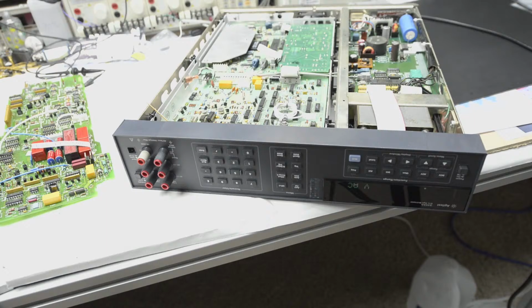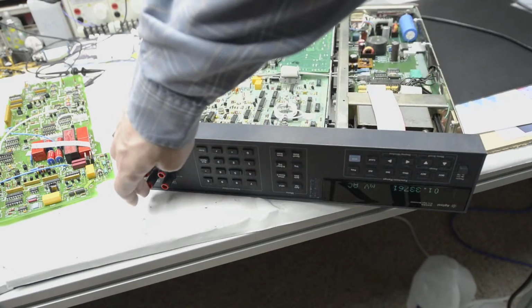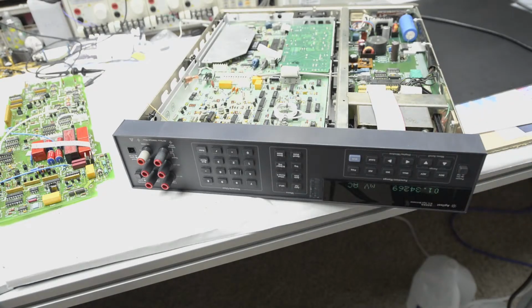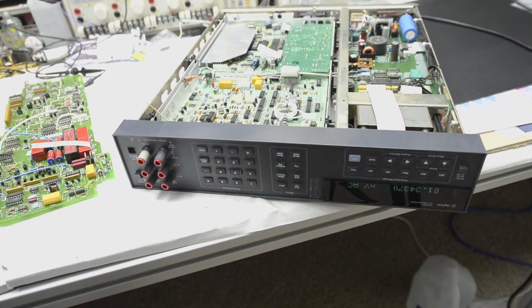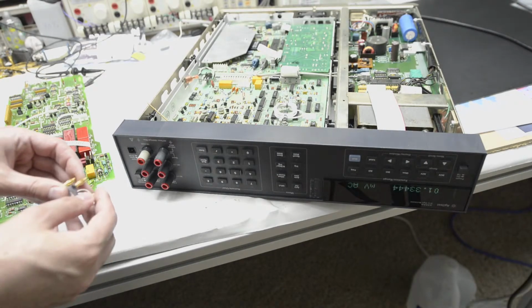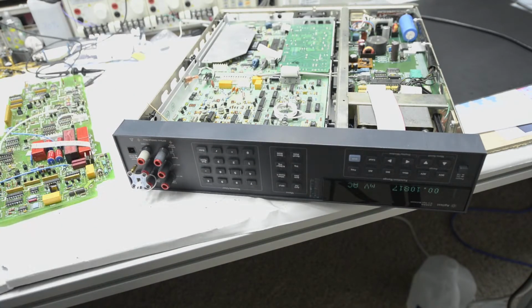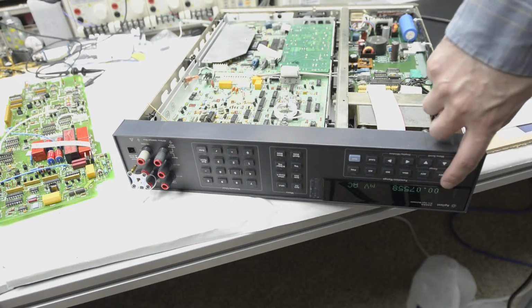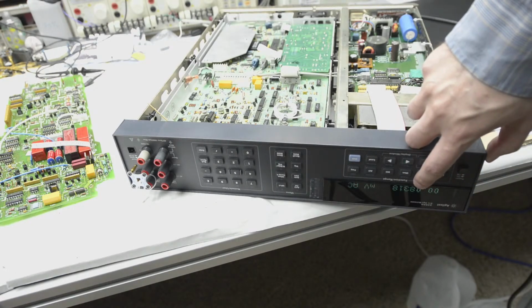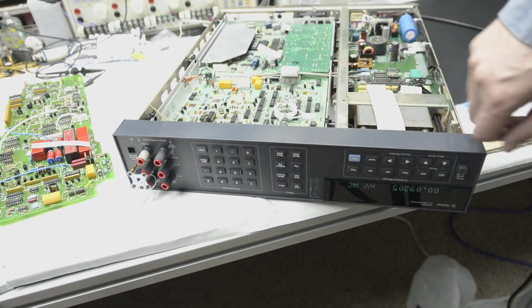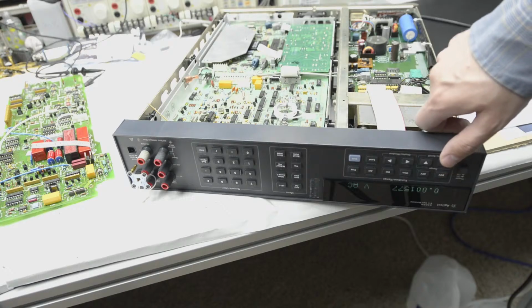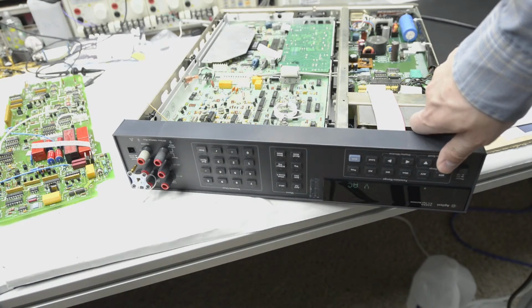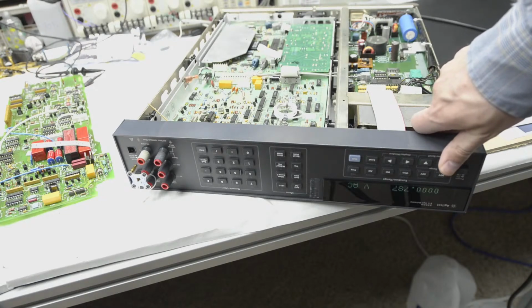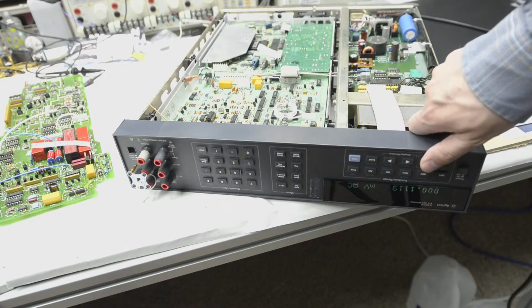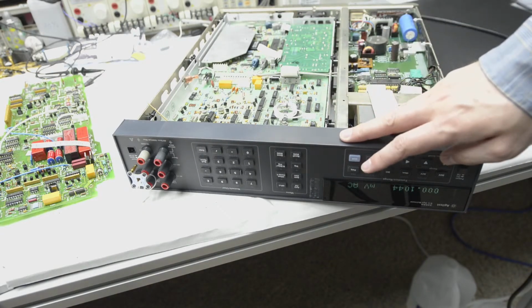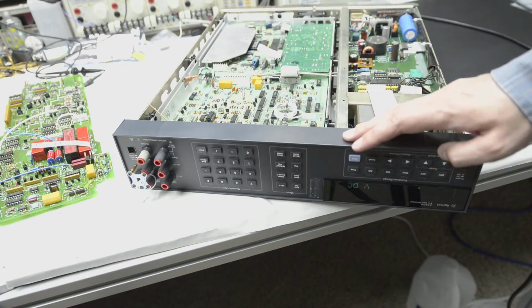And the typical issue with the AC board is you have some bogus voltage even when you have the input shorted. So let's short the input. There. That's my short. And you can see right away, I'm reading like 0.08 millivolts, so that's 80 microvolts or so. Just some pickup. And then if I go to different ranges, there is some value, but it's kind of small. So that's normal. And if you have a broken A2 or apparently A1 as well, you would have some values, like maybe 80 volts when you go to the kilovolt range.